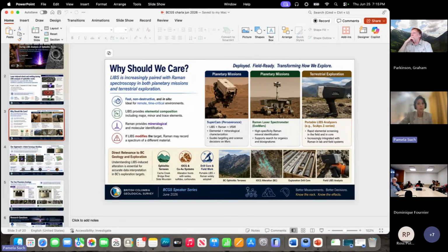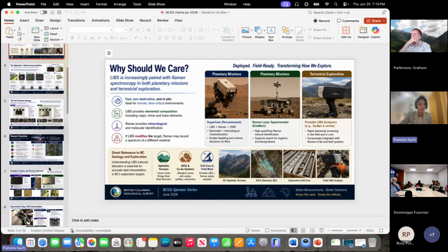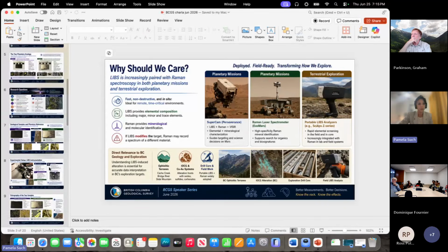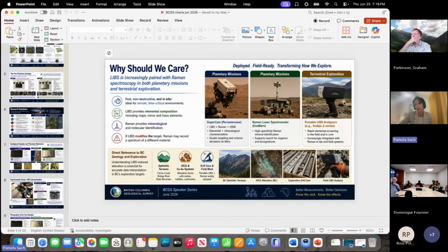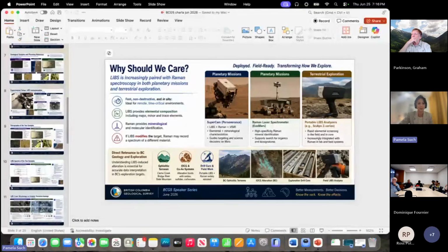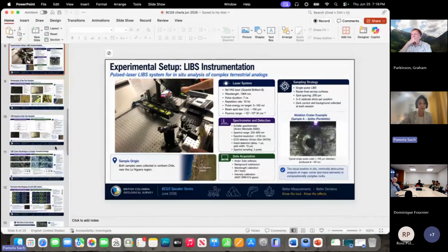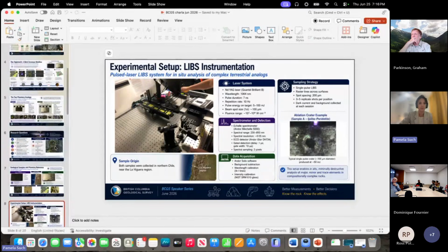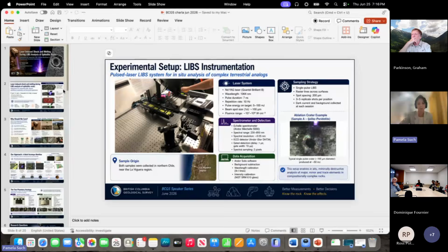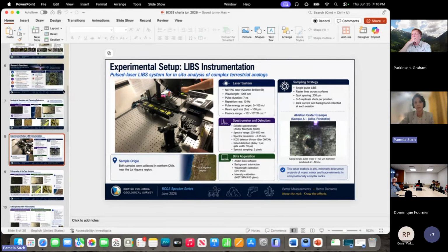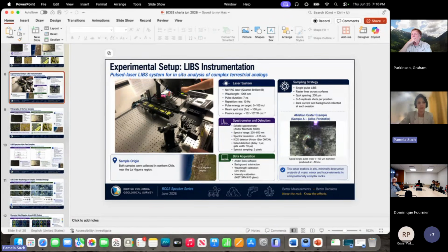I don't know if the people using the instrument know that. I would do 5% or even 2% of the energy power. Or I don't know if the company has preset the software to use 2% so it won't run the battery so fast. I don't know that. That will be an interesting question to ask the company.